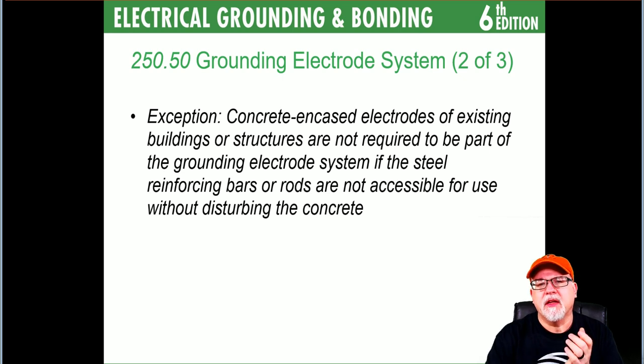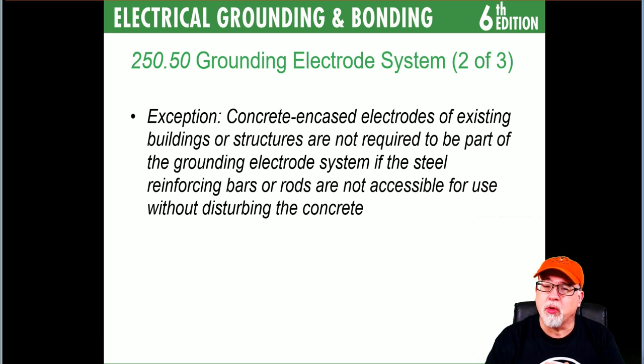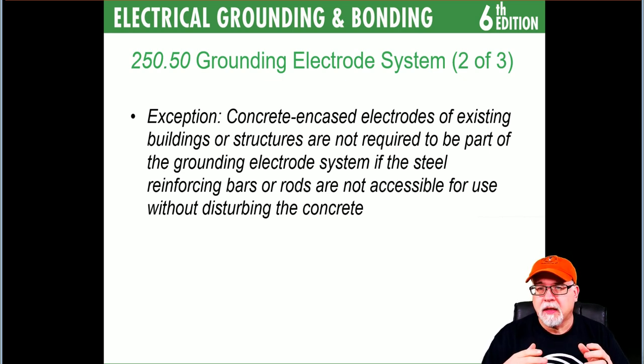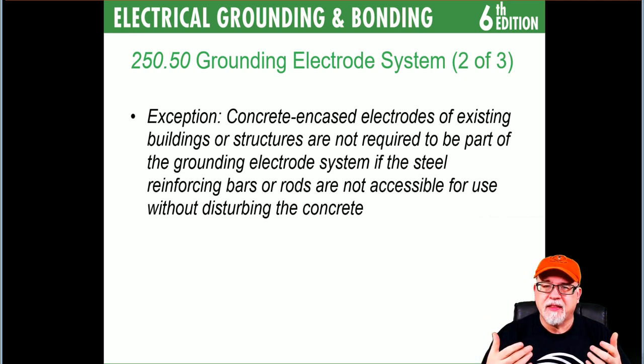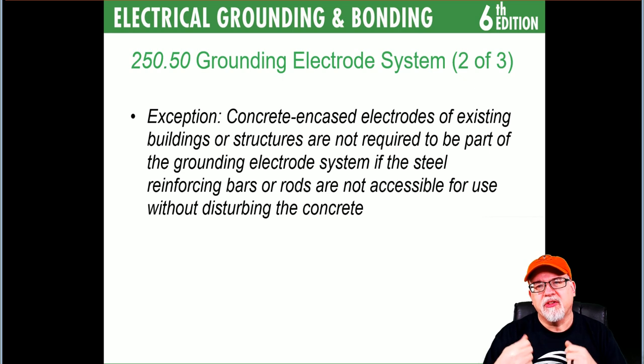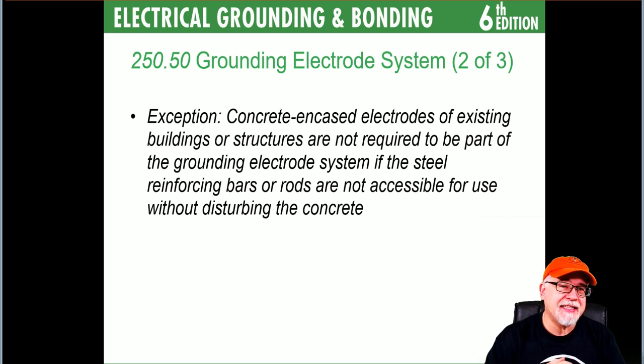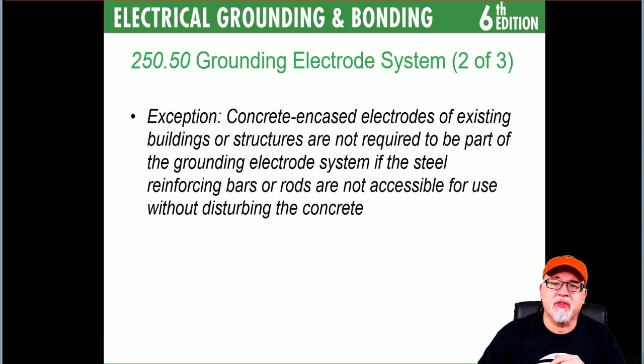There is an exception: concrete encased electrodes of existing building structures are not required to be part of the grounding electrode system if the steel reinforcing bars or rods are not accessible without disturbing the concrete. If the slab is already in place and making connection would require chiseling up to reach the rebar — thus weakening the foundation — then you act like it's not there and install a grounding electrode system per 250.52.